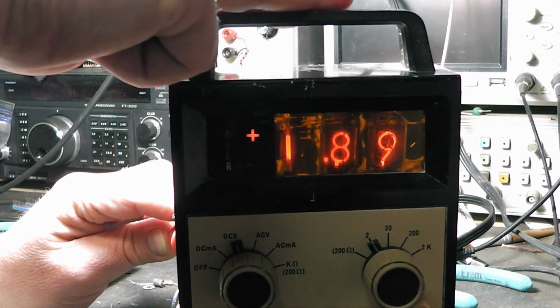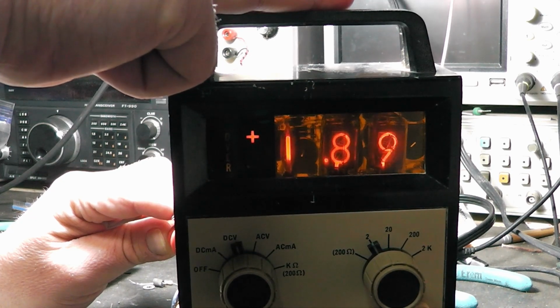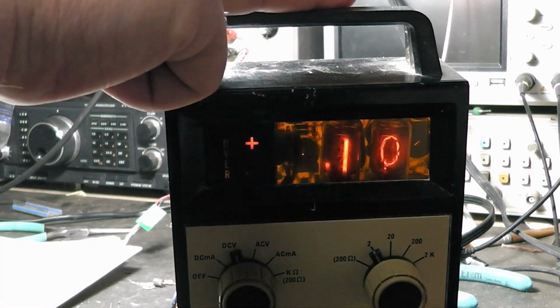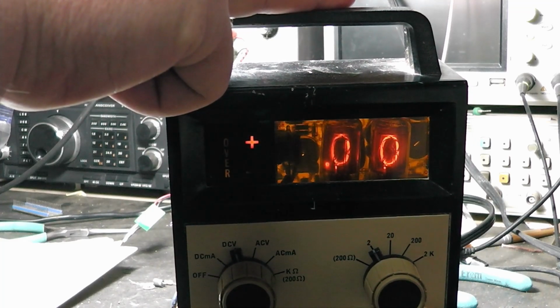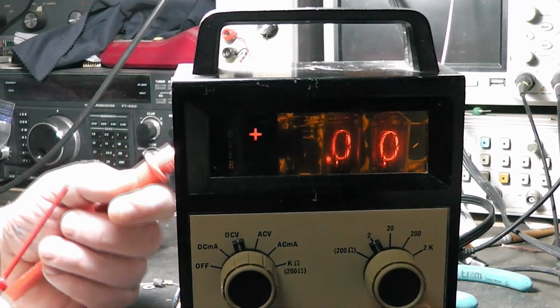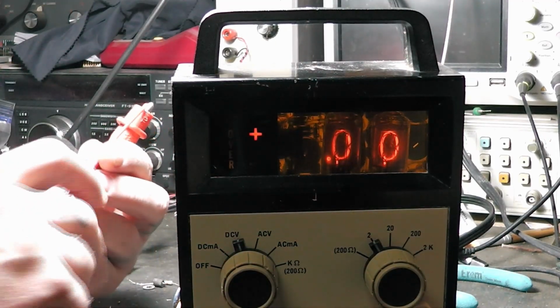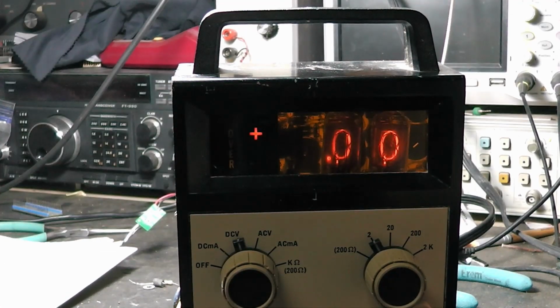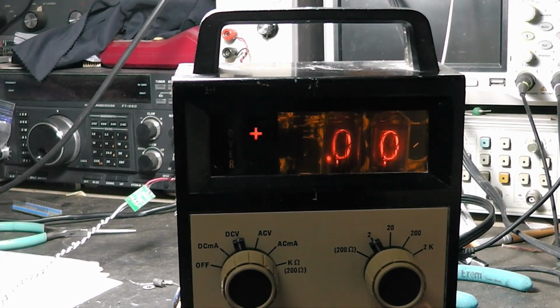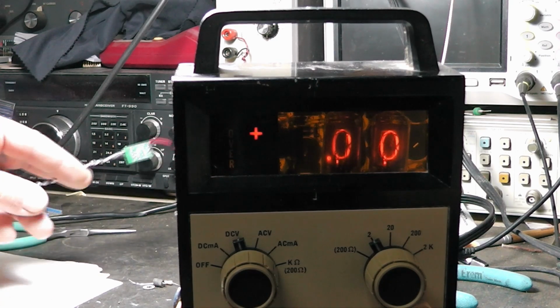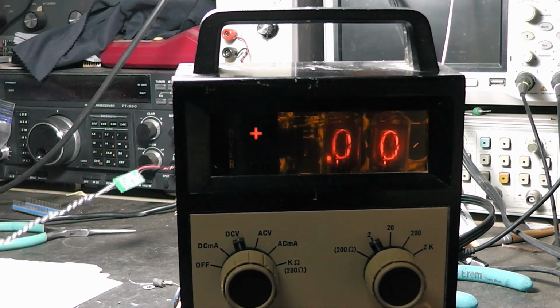Well, I'm looking in the monitor now so I can see this. 1.89. And the back of the thing says 1.87. So maybe 1.88. So what you'd want to do is adjust that DC in the back to match that. But before we do that, we've got better things nowadays. If you have a more modern, pretty good voltmeter, multimeter, or whatever, you can hook it to a known voltage. Or if you have a voltage reference, like I've got, kind of see in the background hooked up here, you can hook it to that.